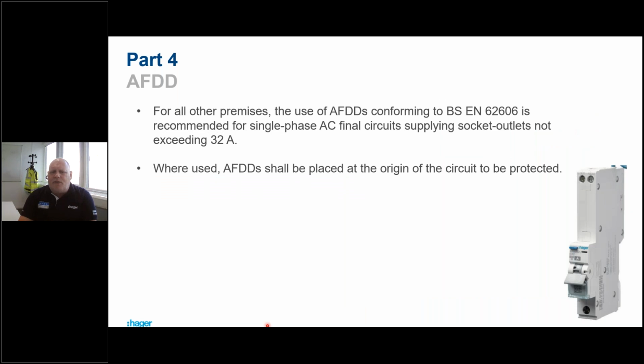Now what they're saying is for all other premises, the use of AFDDs is recommended. So just remember the weighting behind that word recommended, for single phase AC final circuits supplying socket outlets not exceeding 32 amps. So where used, the arc fault detection device shall be placed at the origin of the circuit to be protected. We've got to have 1 per circuit, not 1 per board.